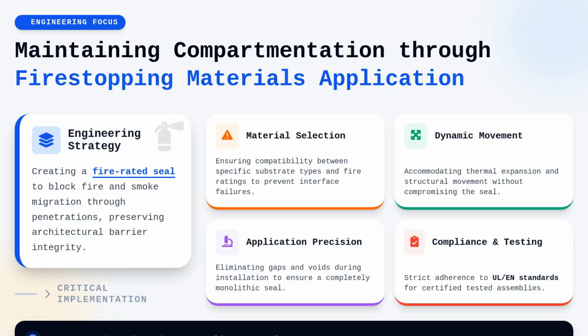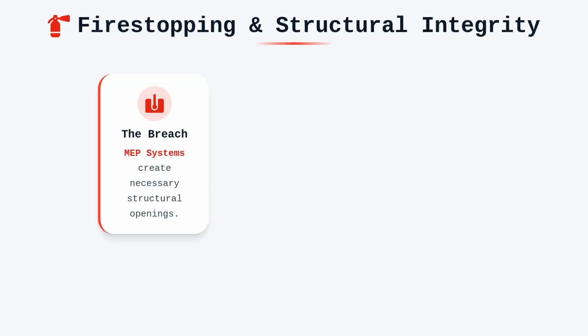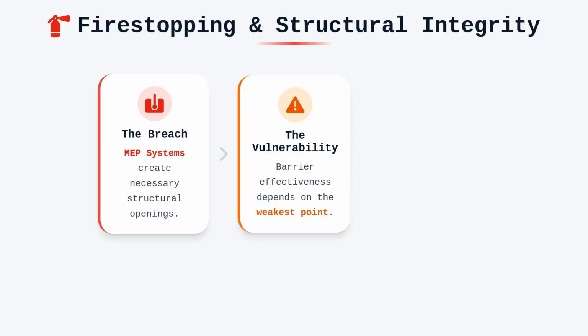Welcome back. We are now narrowing our focus to the critical engineering challenges associated with maintaining compartmentation through fire-stopping materials application. When we discuss fire stopping, we are essentially talking about the integrity of the fire-rated barrier. Every time a building is constructed, we create structural breaches for mechanical, electrical, and plumbing systems. A fire-rated wall or floor is only as effective as its weakest point, which is often the interface between a service penetration and the building element itself.